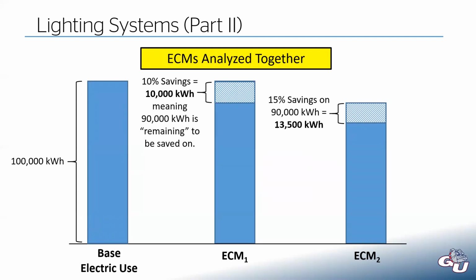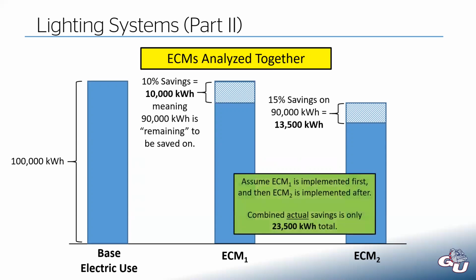So instead of 15% being 15,000 kilowatt hours, it's only 13,500. You have to take a staged approach: assume the first measure is implemented, then apply the second on top of that. So the combined actual savings here is 23,500 kilowatt hours, not 25,000.